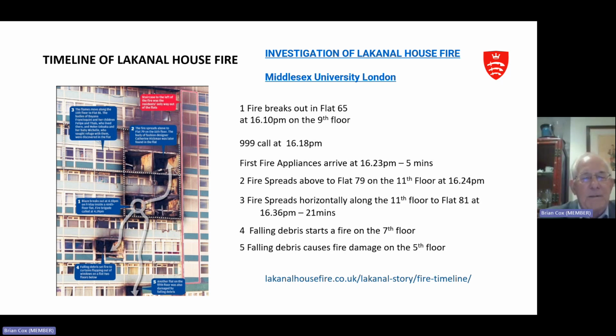So the fire, this is data from Middlesex University. The fire broke out in flat 65 at 16:10 on the 9th floor. And there was a 999 call at 16:18. And the first appliance arrived at 16:23, which is 5 minutes, which is very quick. But the fire had already spread from flat 65 on the 9th floor up to flat 79 on the 11th floor by 16:24. So within a minute of the fire appliances arriving, the fire had already gone up 2 floors.